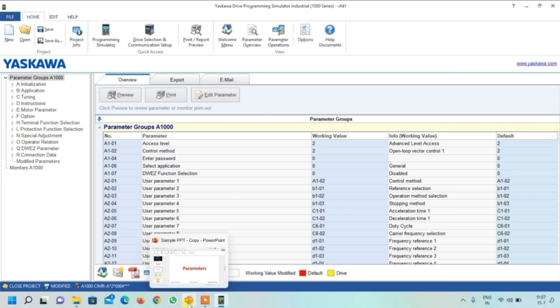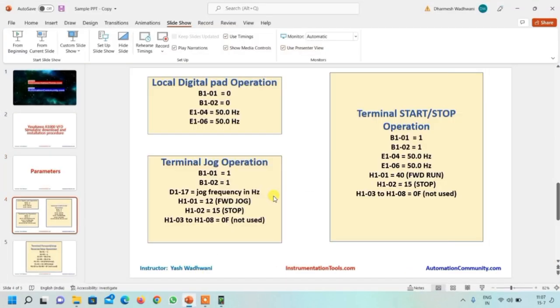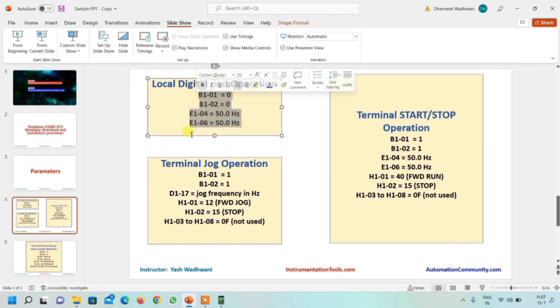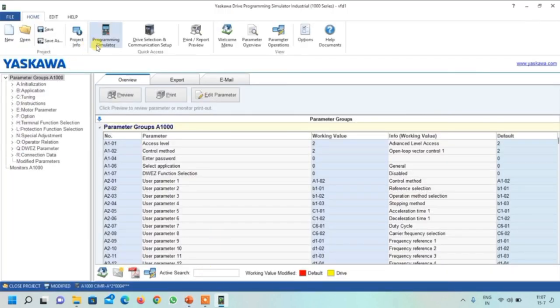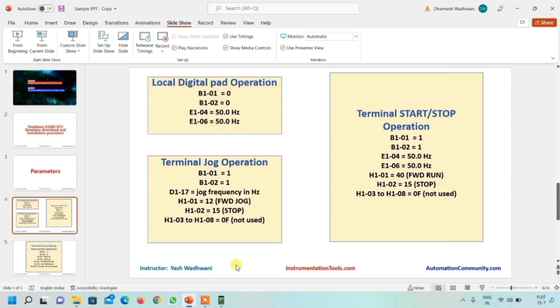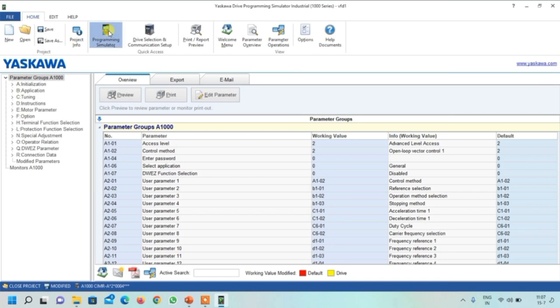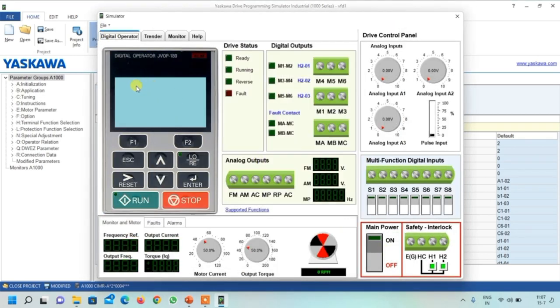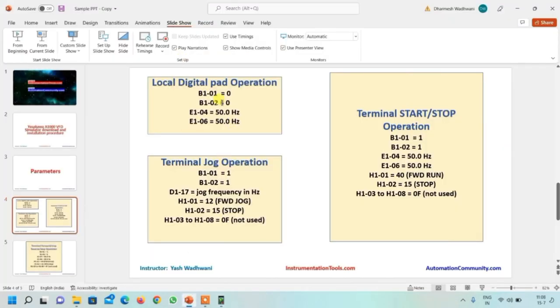I have tried different cases and found I can use four operations with this simulator. The first operation is local digital keypad operation. If you set these parameters, you will be able to do local digital keypad operation. To operate the drive from the keypad, double-click on the parameter you want to change.